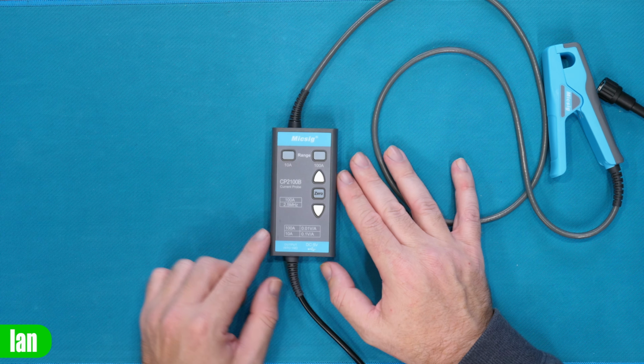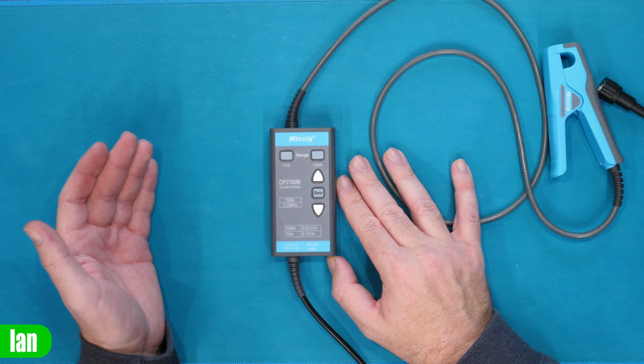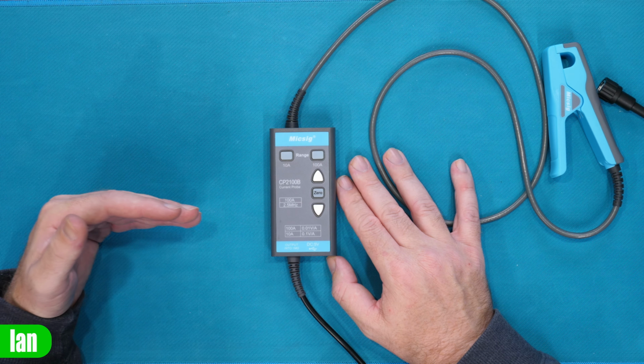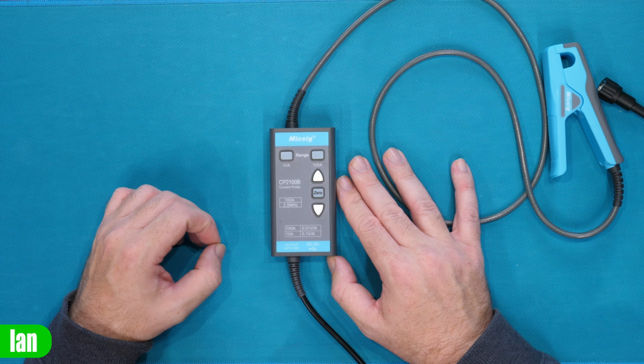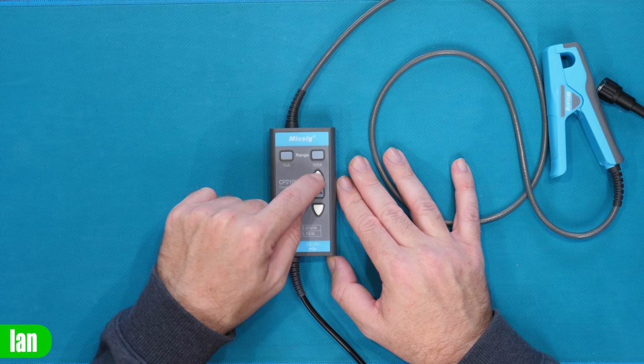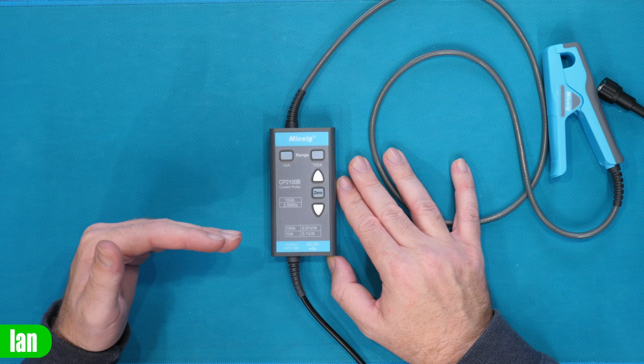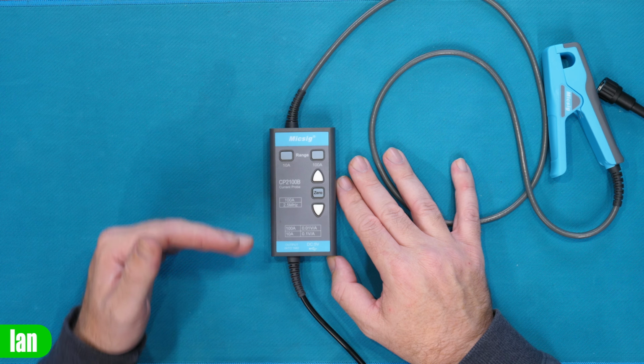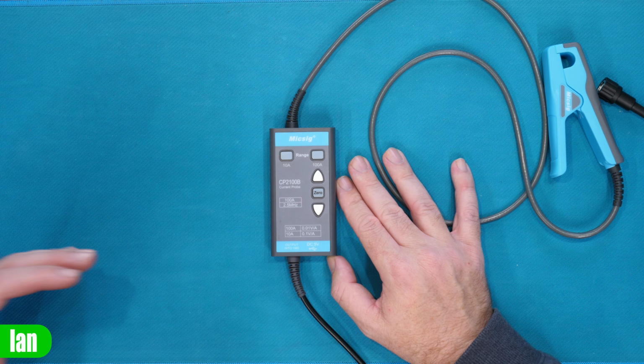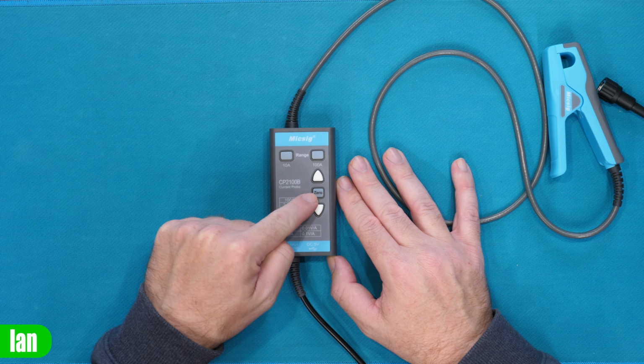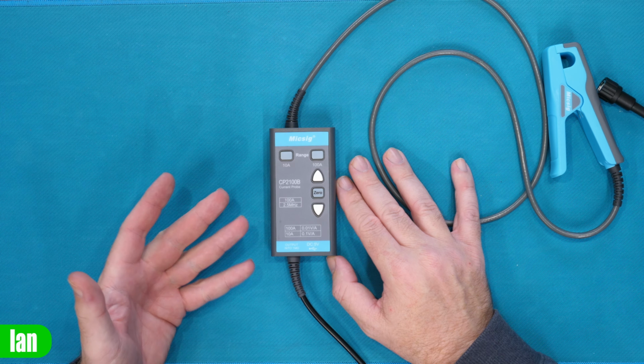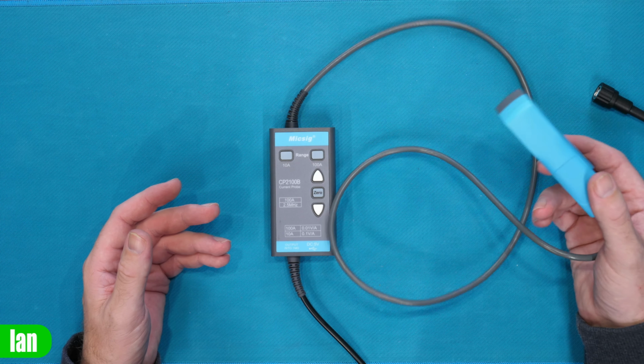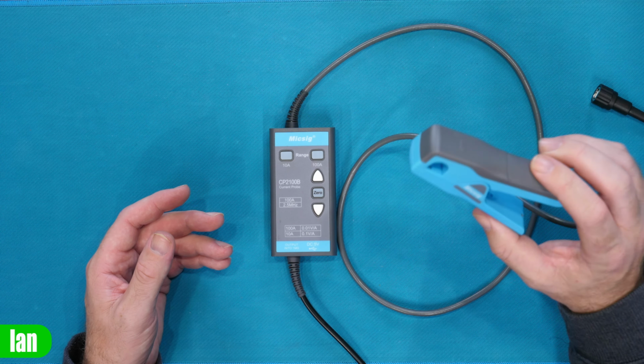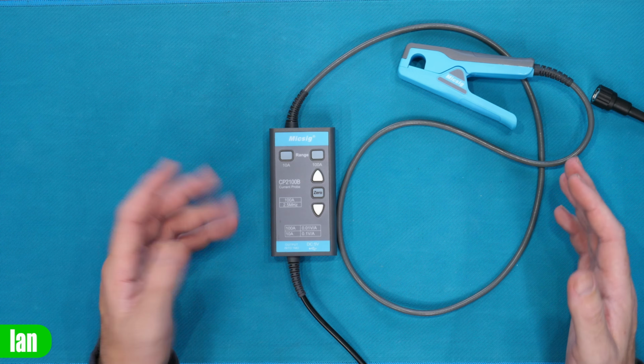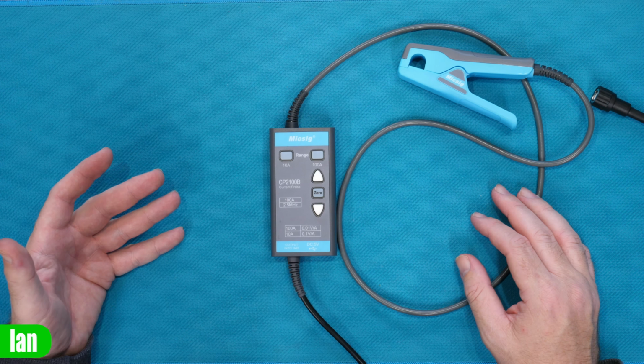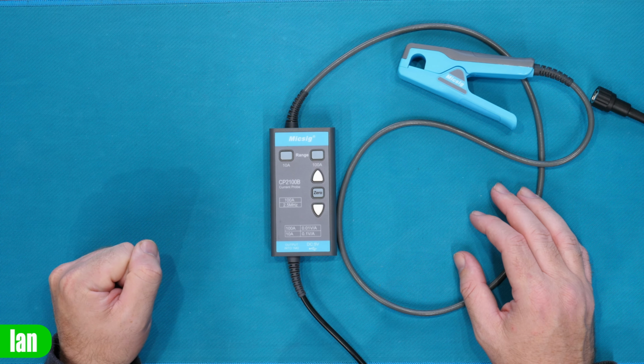Looking on the probe itself, we have our 10 amp and 100 amp selection, which again selects what range we want to be looking at and the accuracy is going to behave in. We have our adjustment here, which is our reference adjustment, which we'll take a look at a little bit later, but you can basically adjust the reference on the probe as well as on the scope as well. And we have a 0 button. You will need to 0 the probe before it's used, and you should do that in free air. So what you would simply do is have it away from anything electrical before using it, hit the 0, allow it to calibrate itself, and then you're able to use it.